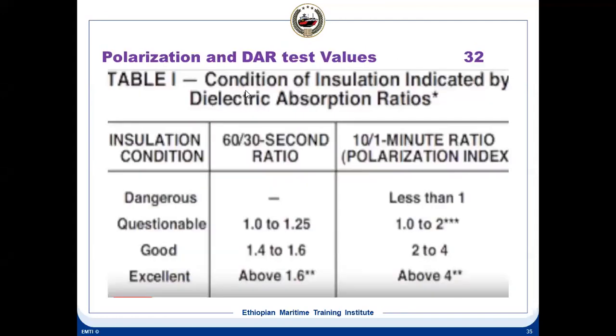Okay, sir. Thank you. Why are we not doing this PI test for low voltage equipment? I mean, why is it only for high voltage? Because this same problem can happen also for low voltage. No, because the polarization index test is done with high voltage equipment. We are using a high voltage Megger for this. On 440 volt ships, we need only a 500 volt Megger. And the insulation requirement is totally different in the case of high voltage and low voltage.